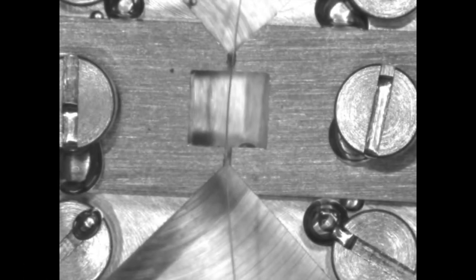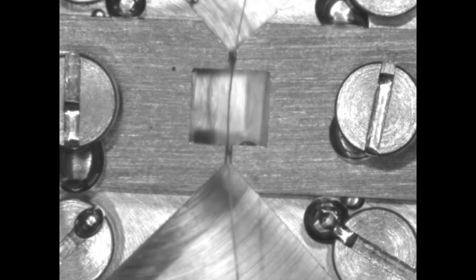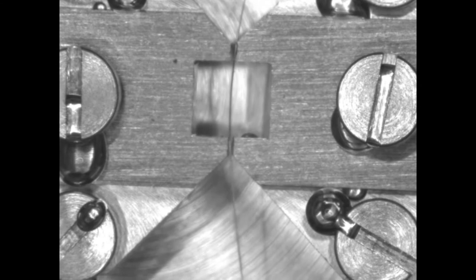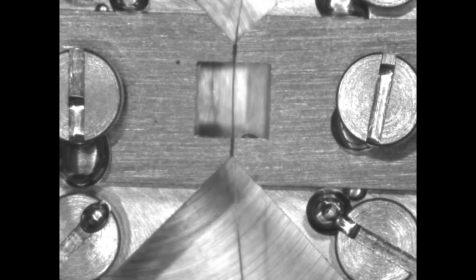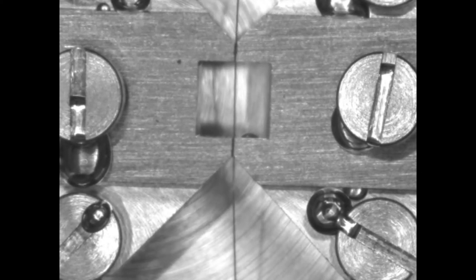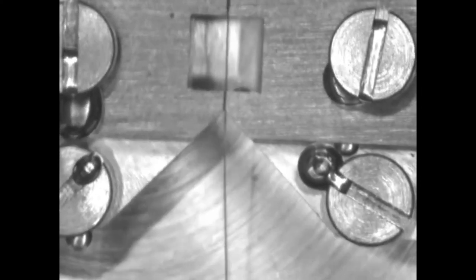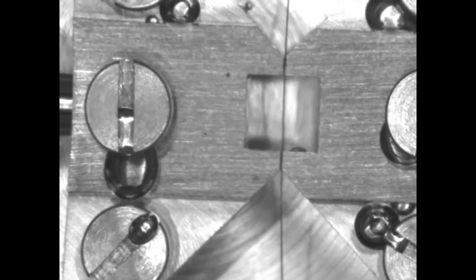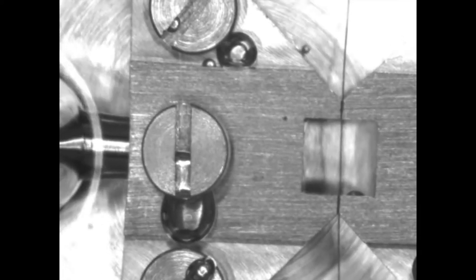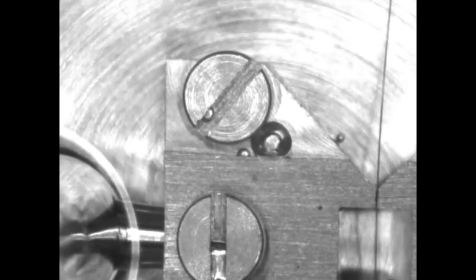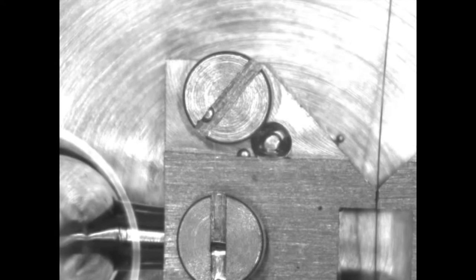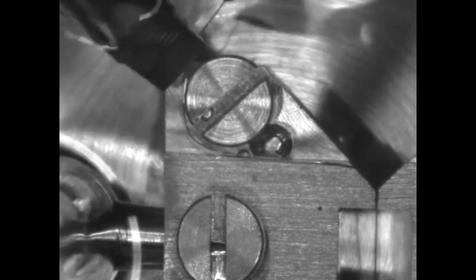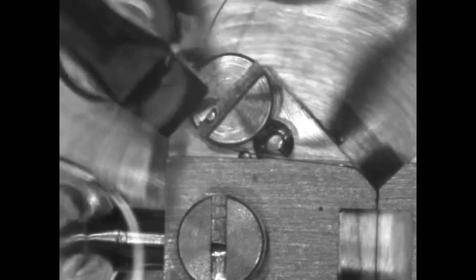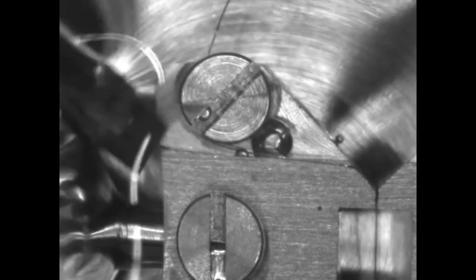After dissection, we need to then mount the vessel in the 620M chambers. You will place a section of the wire between the jaws. You just need to clamp it in place. You do not need to press too hard as you could damage the force transducer. Now on the micrometer side, you will need to secure one end of the wire. It does not matter which side. Place the wire under the screw and tighten the screw in a clockwise direction.